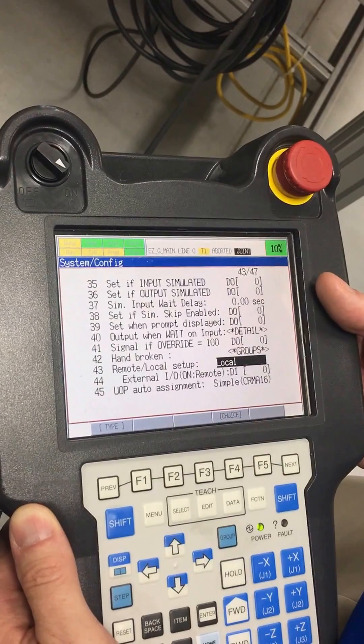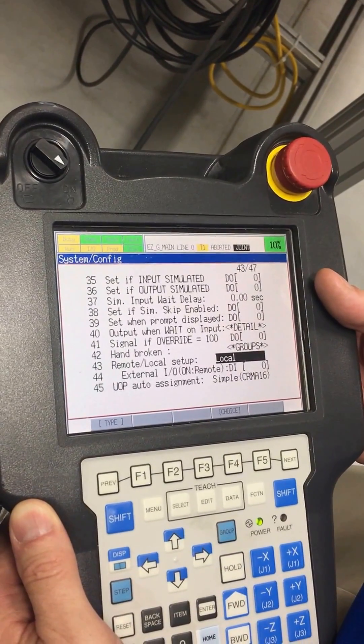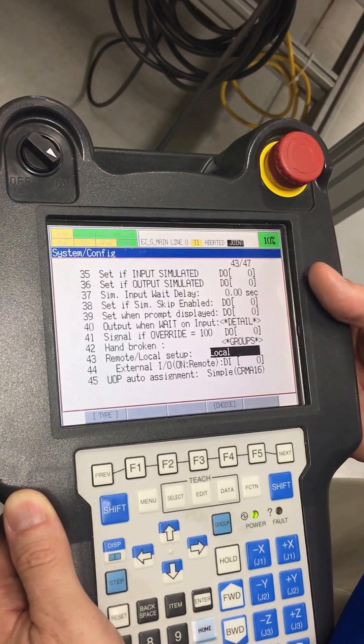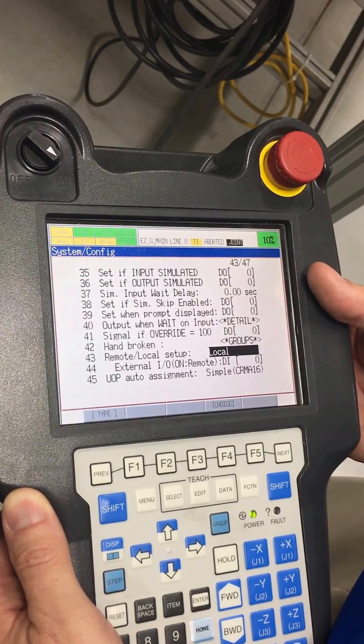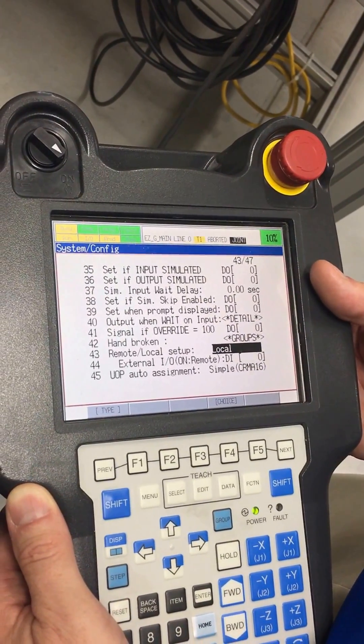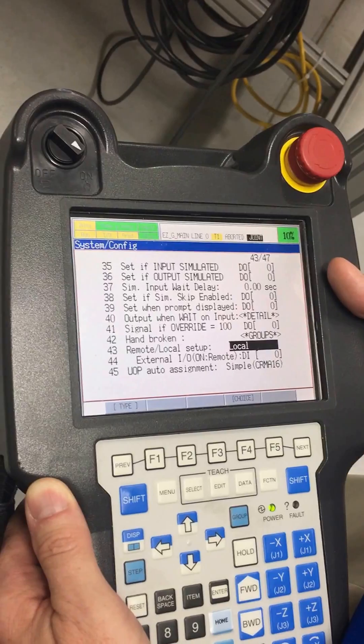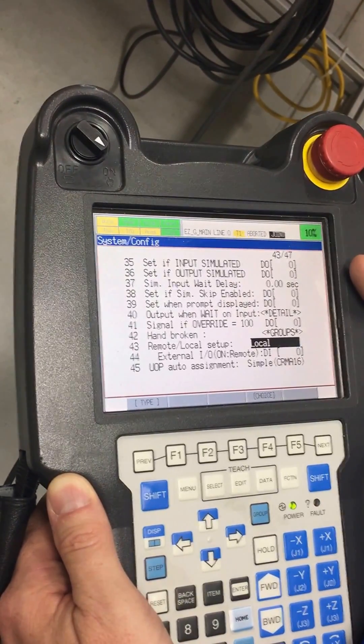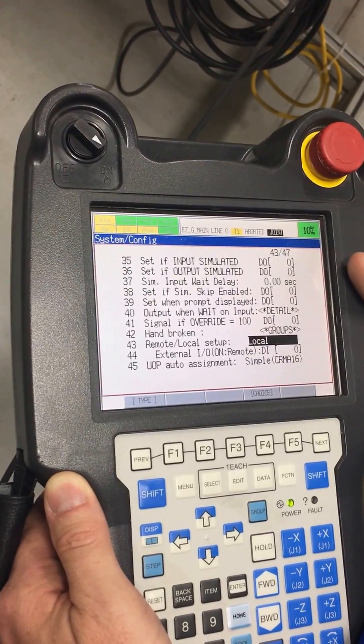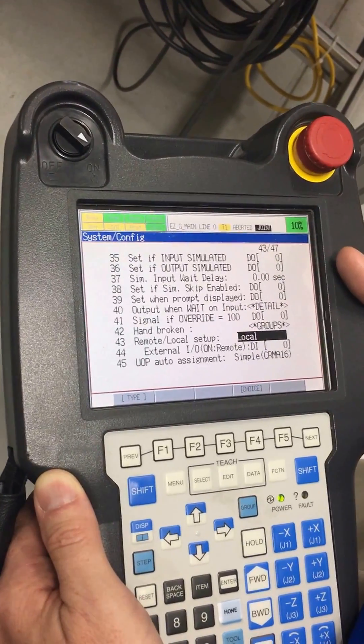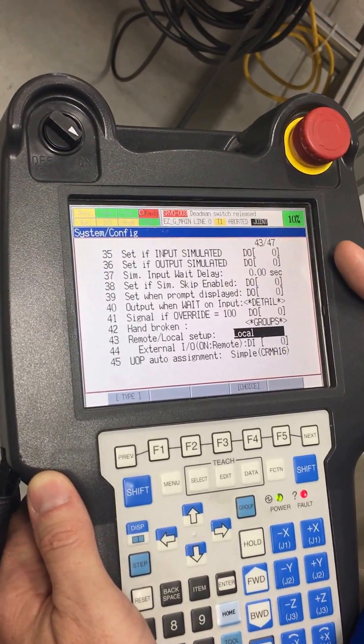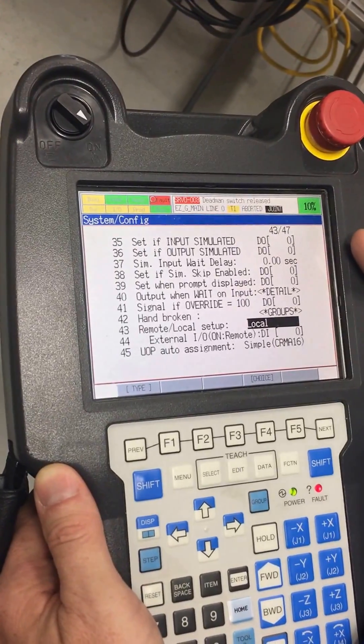In other words, this was feeding our safety relays in class here and we couldn't clear the faults because it was looking for some external information, either over Ethernet IP or hardwired, and it wasn't satisfying that condition so we could never clear our safety circuits.